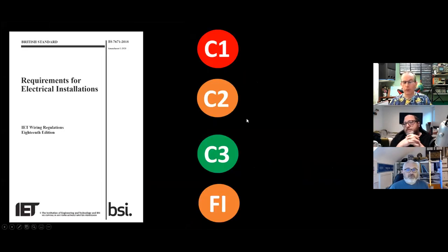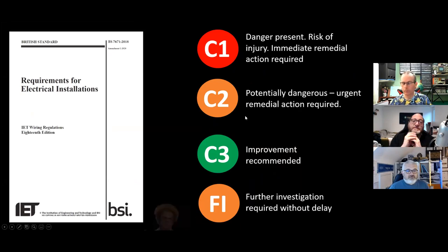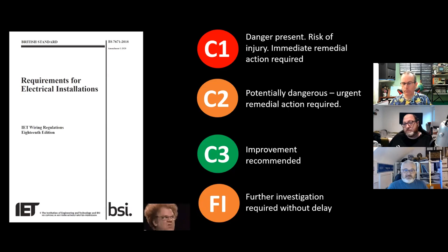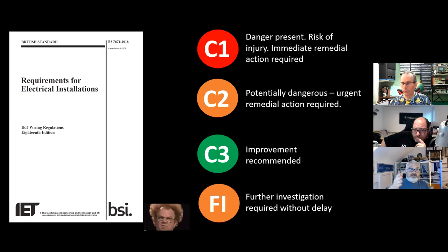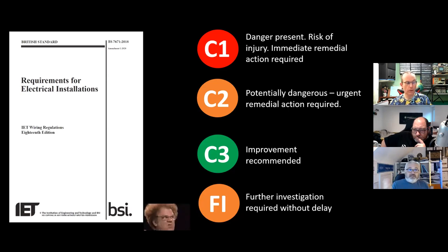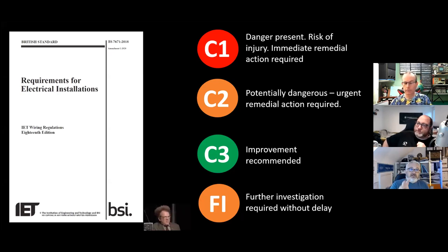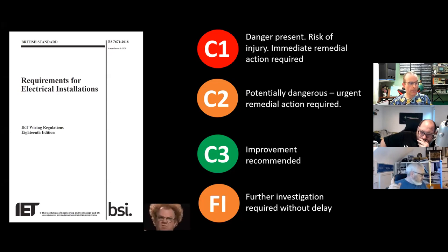Whether you're 20 or 30 years in, we all know these codes and they cause a lot of confusion. The Code Breaker book does have codes for the DNO intakes. The DNO intake is certainly something we need to inspect because it's in the schedule of items to be inspected. It's imperative for the applied safety measure — we do a Zs test, a PFC test, we make sure there's sufficient energy from the external earthing to trip circuit breakers.